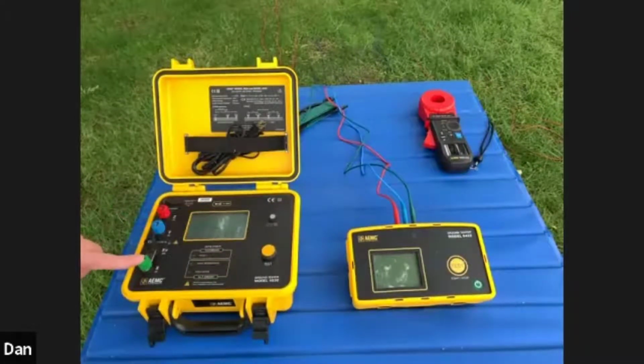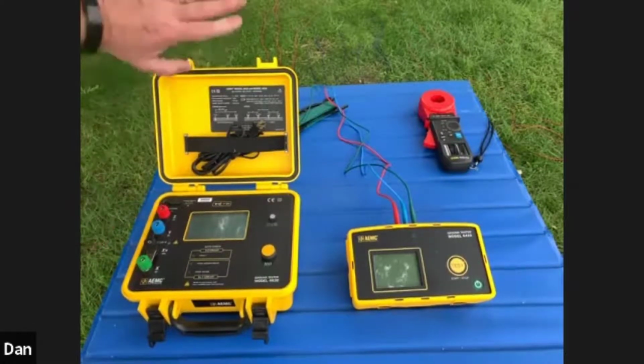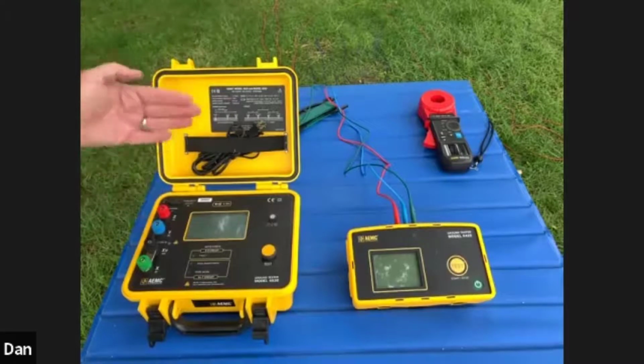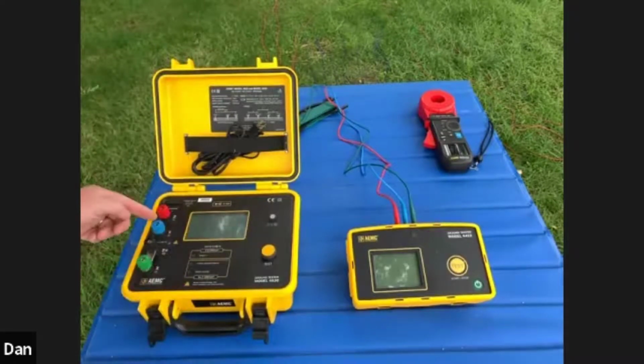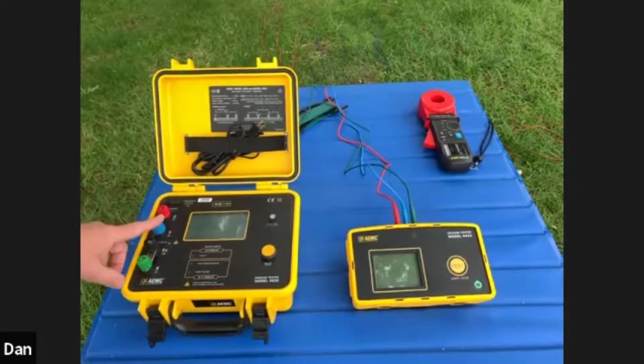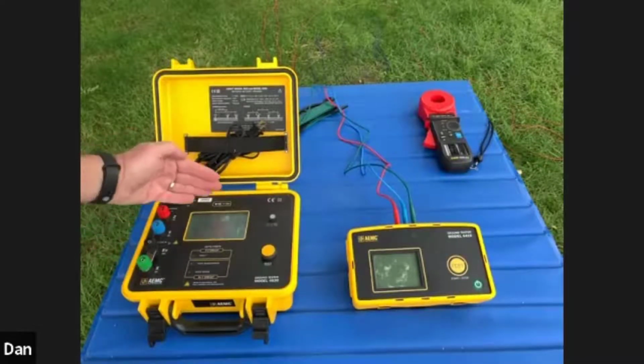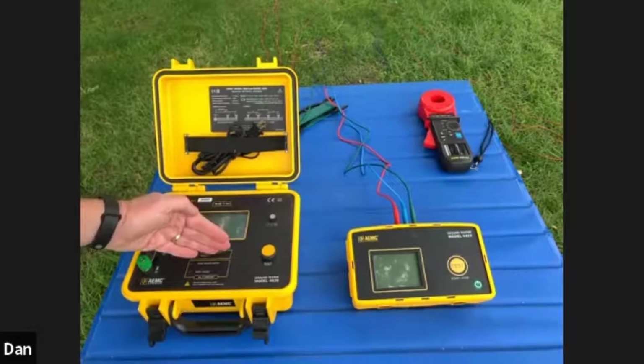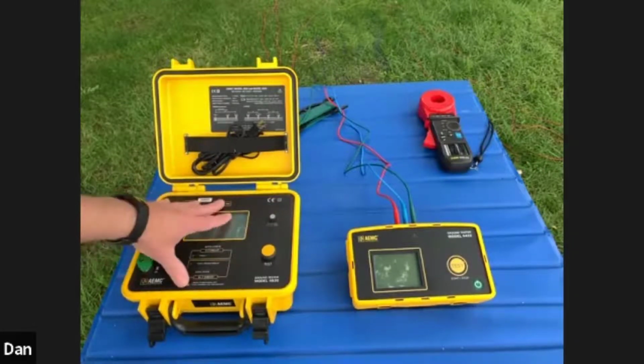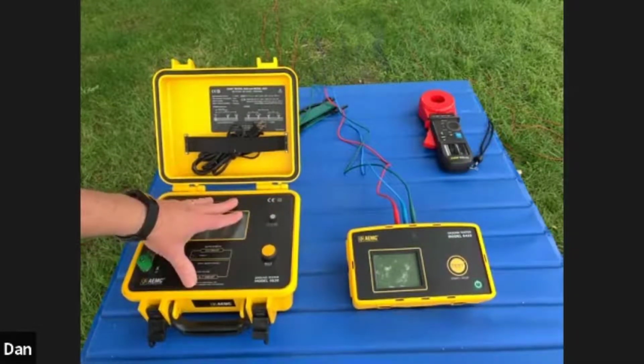With this one, we have a grounding connection - the red lead, or the Z lead, which is the furthest one out and stays stationary - and then the blue one, which moves in various increments. We did what's called a 62% test, taking measurements at 72%, 62%, and 52%, and came up with a reading. So this is what we used last time.